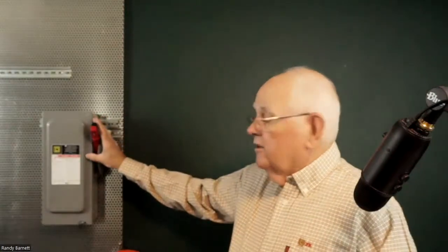So I need to find my piece of equipment, and it's not a panel board, it's not a motor control center, and it's not medium voltage equipment. So there's really only one grouping left, and it says other 600 volt class, 277 through 600 volt nominal equipment. And so this would be 480 volts equipment. This disconnect is rated for 480 volts. So it would fall in this line for other equipment. And it tells me in that line that it's PPE Category 2, and that my arc flash boundary is 5 feet.